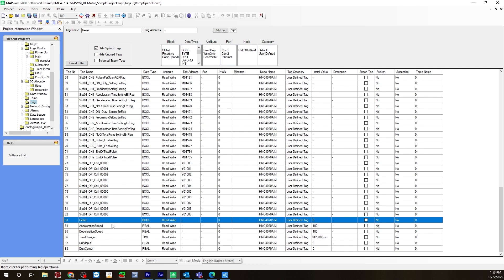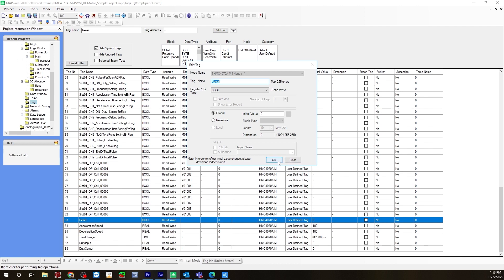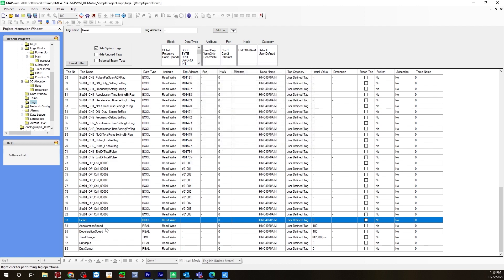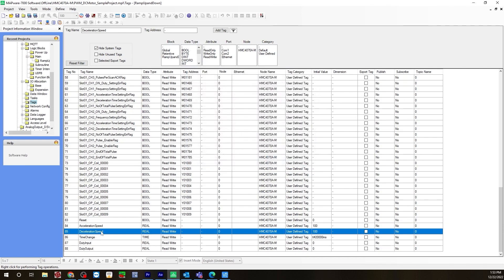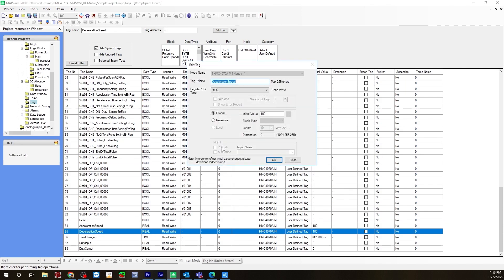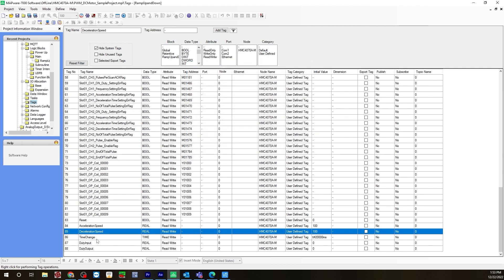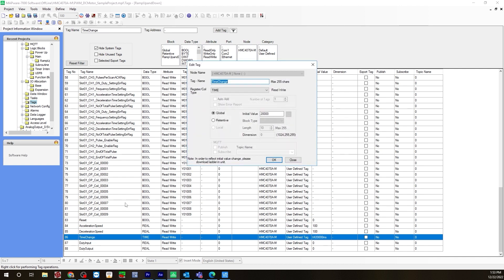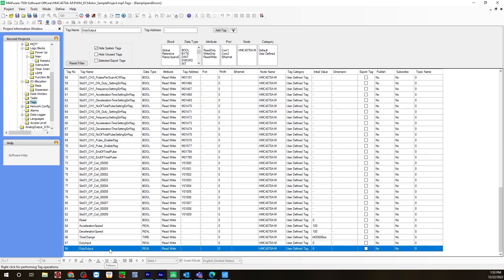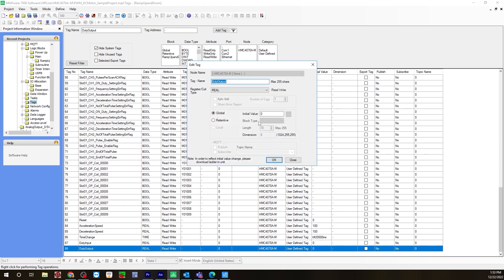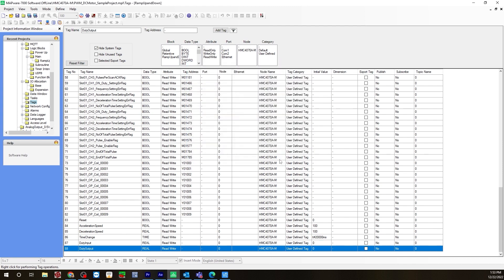For the reset button, that is a register type bool with no initial value. The acceleration speed I have set to 100, as that is the max duty cycle, and the deceleration I also have set to 100, and I'll get more into that later when we build the logic. Time change I have set to 20,000 milliseconds or 20 seconds, and I'll explain that as well. For the duty cycle input is a real register, and duty cycle output is also a real register.